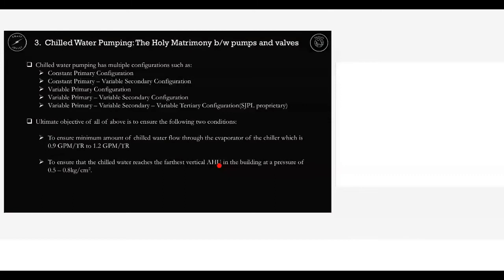That means there is an increase in the system pressure, the water pressure in the chilled water line. And that water pressure, as you see in the last point, is 0.5 to 0.8 kilogram per cm square. You need not increase the pressure beyond this range, and that is actually wasting energy. This changes from case to case, building to building, but if that is the generic number we follow, at the farthest hydraulic point in the building, your comfort is established and your area is cooled.